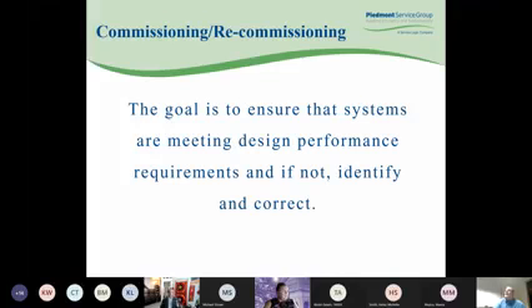The goal of commissioning and recommissioning is to ensure that systems are meeting design performance requirements, and if not, identifying and correcting why. Equipment and system sizing is based on calculated heating and cooling loads. Is the space being used for the design purpose? Was this facility bought, and at one point in time it manufactured textiles and now it's being used for another type of product? So what are we using the building for? Every installation is different and not a one size fits all. So you take the opportunity with recommissioning to make sure that the equipment is performing at its top efficiency.